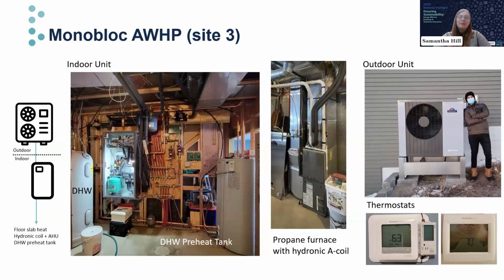And here's our monoblock air-to-water heat pump system that has the space conditioning and domestic hot water preheating. The units that we did install for monoblock systems were provided by the manufacturer, also with an indoor unit. This is not technically required for a monoblock, but this particular manufacturer has a lot of their controls built into the indoor unit, so it is an integral part of this specific model. And that's the large box that's brightened by a light on the left-hand side. That box interfaced with the domestic hot water preheating tank, which is on the right side of the left-hand picture, and also had lines that went across the room to an air handler, which had a propane furnace and the hydronic coil to provide heating and cooling through a ducted system.